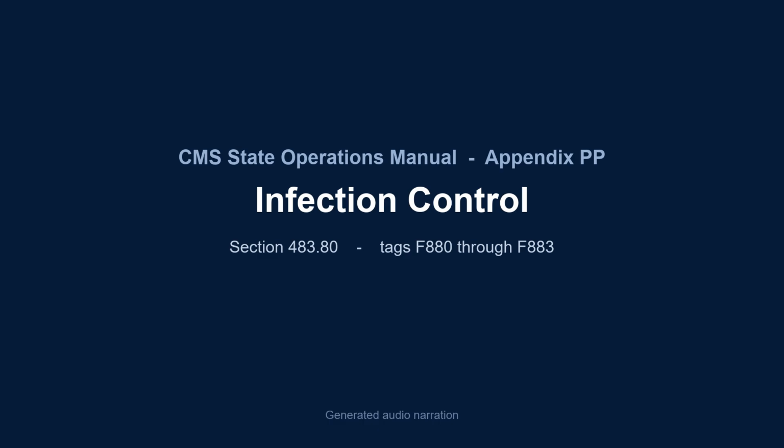39. Low-level disinfection is traditionally defined as the destruction of all vegetative bacteria except tubercle bacilli and most viruses, some fungi, but not bacterial spores. Examples of low-level disinfectants include EPA-registered hospital disinfectants with an HBV and HIV label claim. Low-level disinfection is generally appropriate for most non-critical equipment.